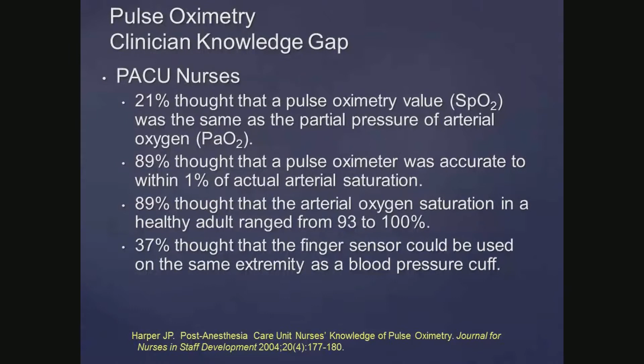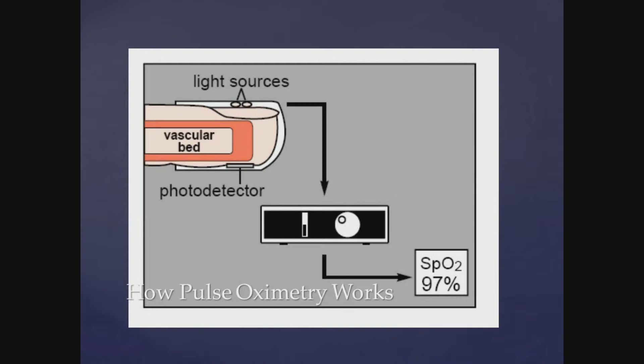So again, what you're using with pulse oximetry is you're shining two light sources, one infrared, one visible light, through a vascular bed, detecting the signal on the opposite side. We know that the signal can either be absorbed, reflected, or transmitted through. If it's a wavelength of light specific for oxyhemoglobin, it's going to be absorbed by the oxyhemoglobin within the vascular bed prior to reaching the photodetector, and that's basically how pulse oximetry works.